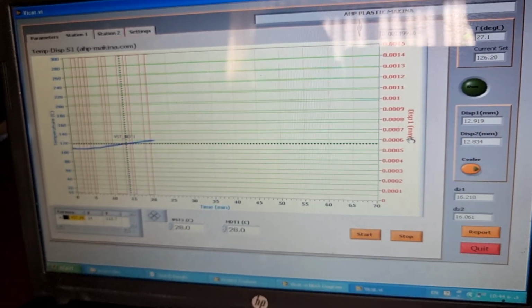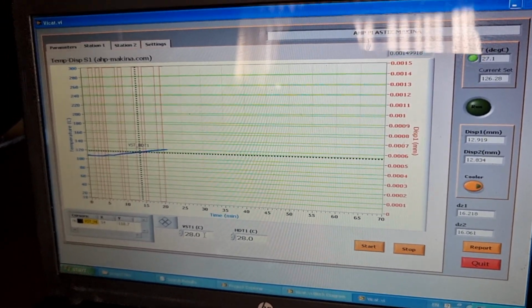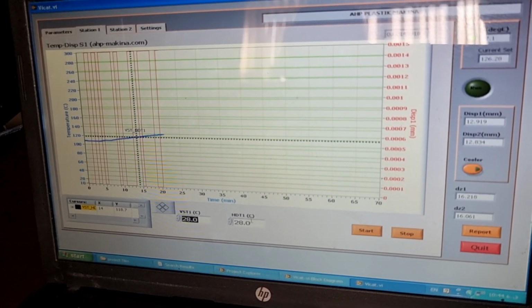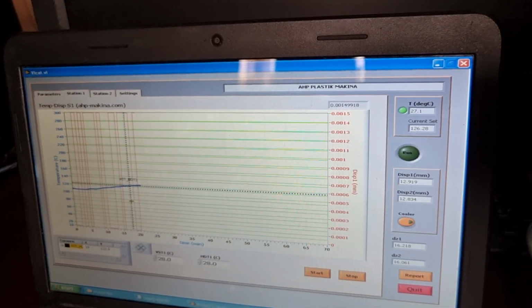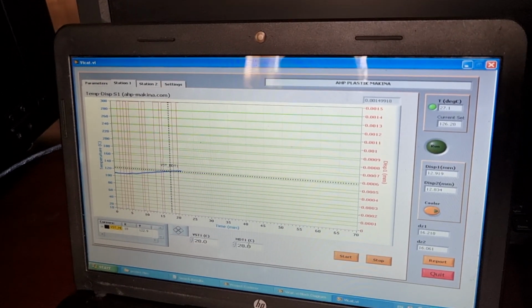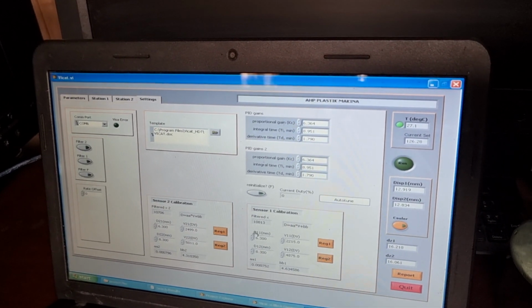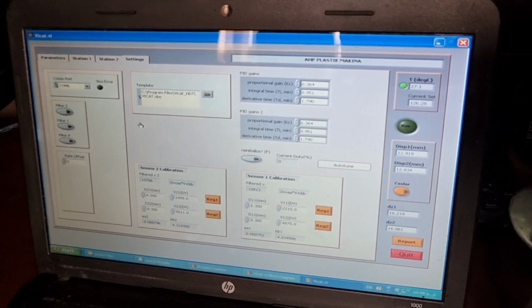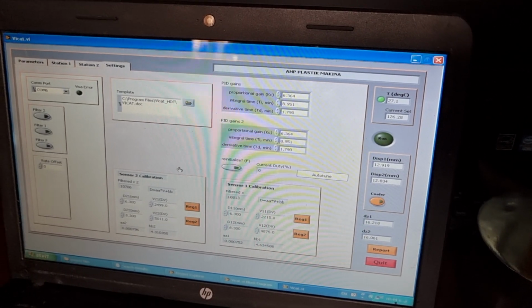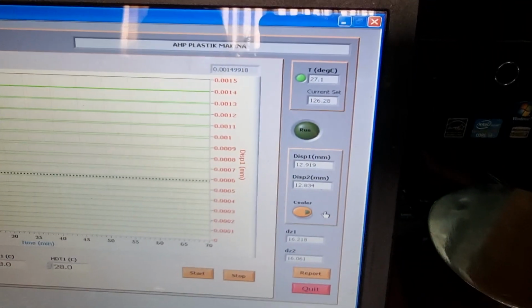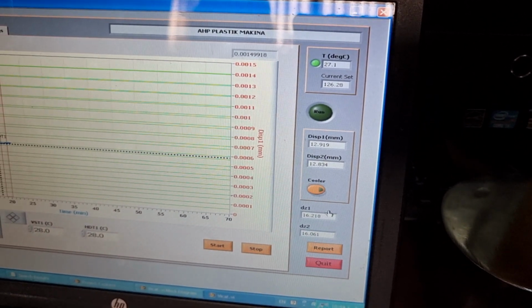Station 1, you have the graph including data for temperature, time and displacement of the sensor 1. You have two parameters named VST, Vicat softening temperature, and heat deflection temperature here. After the finish of the test, you can easily read the data of the graph here and set and read the values for VST or HDT for that specific channel here. You have a setting page, calibration of the sensors, and tuning of the temperature, calibration of the temperature. All parameters are here in the setting page. On the right side, you have displacement of two sensors, and you have control of the cooling water, and all data you will have in the software. Yes, I'm going to start.